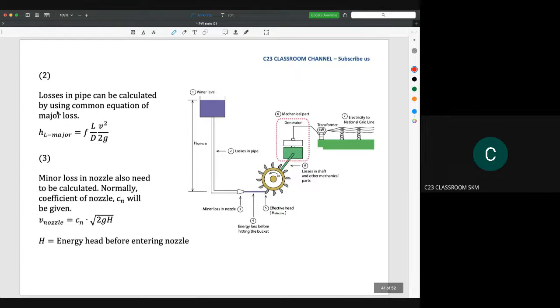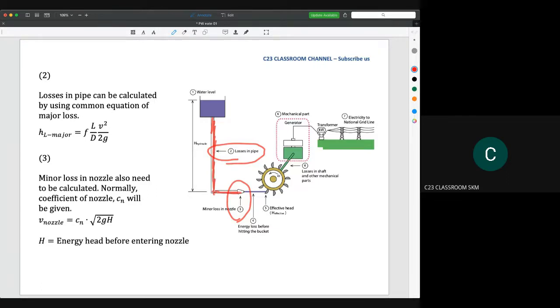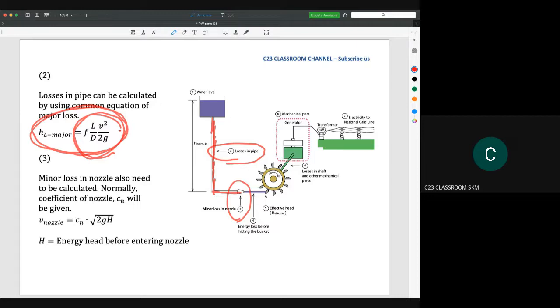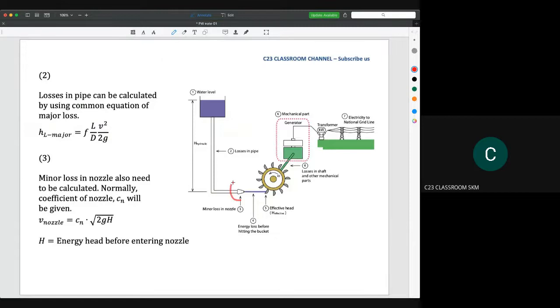For situation number two, when water flows inside a pipe, you need to know how to calculate the major loss. Please revise fluid mechanics one for this. The equation for major loss is f·L/D · v²/2g. Bear in mind that the velocity v here is the velocity inside the pipe, not the velocity of the water jet. You must be careful about which velocity value to use.